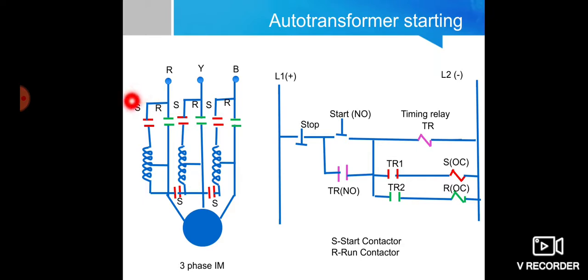Here you can find S is for the starting purpose when you are finding the auto transformer in the circuit. R is in the running position, the contactors that have been used in the running position, where you find the full line voltage appearing across the stator. Similarly, you find a timing relay coil over here which is getting energized initially. While starting, this S operating coil is energized, because of which all the contacts related to S will get closed, and after a certain interval of time, the R coil will get energized, which will eventually make the contacts R close, thereby giving the full line voltage to the stator circuit.